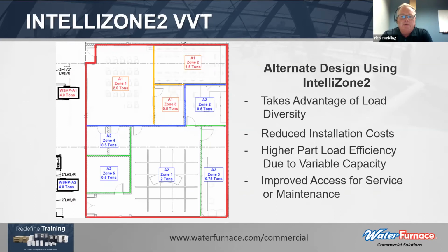An alternative to this would put 2 water source heat pumps, variable speed Versatechs, located in the hallway or in the corridor. It takes advantage of the load diversity. Because this is a classroom and a studio area, it's highly unlikely that they're all going to be occupied at the same time or have the same high density load requirements at the same time.